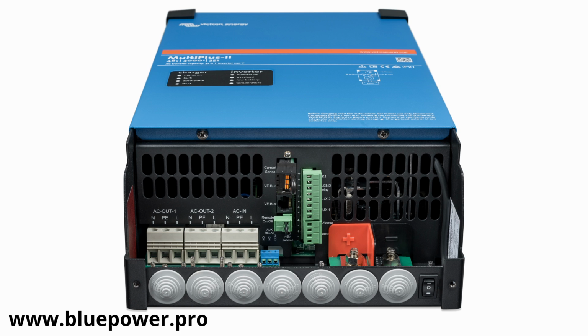So that can be used for non-essential loads or high loads that you want to disconnect from the system when there's a power failure. That's the same as connecting it before the inverter directly onto Eskom. The AC out 2 output can also be programmed to stay on during load shedding, depending on battery state of charge or whichever state you set.